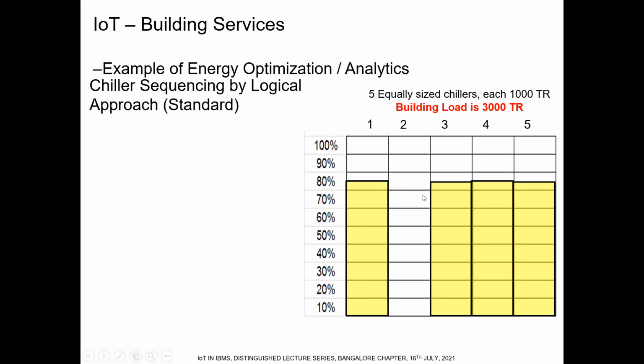The chillers themselves, on their own capacity control method, are operating at 75% of their load. The maximum capacity is 1,000 tons, whereas each is operating at 75%. So 750 tons per chiller times 4 chillers, the building is now operating at 3,000 tons, which is the building load. Now the BMS has to make a decision.